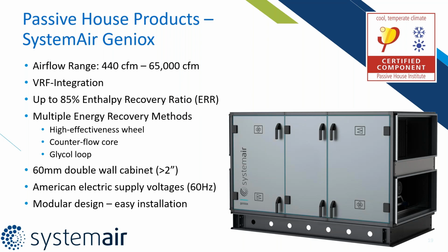This is a 60 millimeter double wall cabinet, which is just greater than 2 inches. We can do all American supply voltages at 60 hertz. So that means 480 3-phase, 208 3-phase, doesn't matter. This actually comes as a modular design, so it's really easy to install in a tight space if you need it. So we can install this unit indoor or outdoor, and it's intended for outdoor, but there's no problem mounting it indoor. And like I said, it's modular, so you can piece it together on site if you need to.